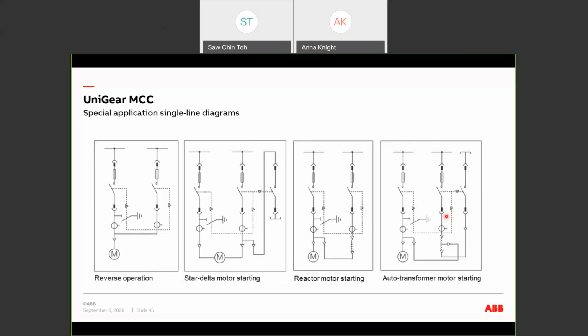Other than direct online switching, we also support other solutions for motor starting, depending on your requirement. For example, if you have forward and reverse starting motors, we can have the design to meet those requirements. We can also support star delta motor starting, reactor motor starting, and auto transformer motor starting.